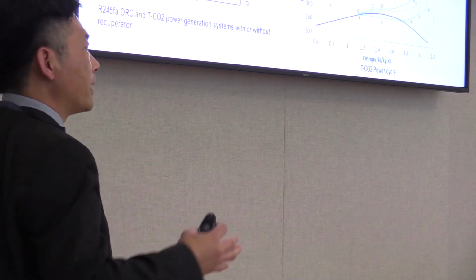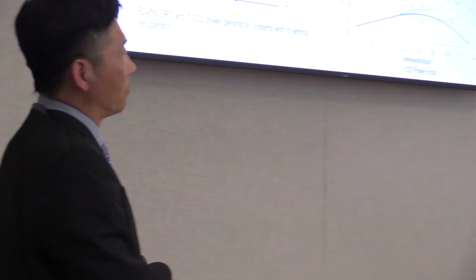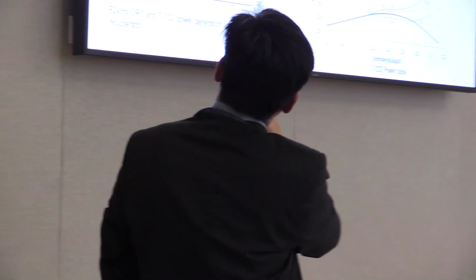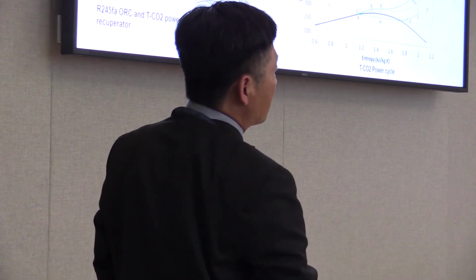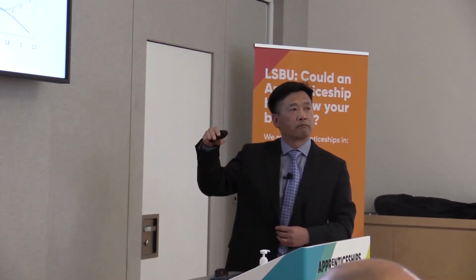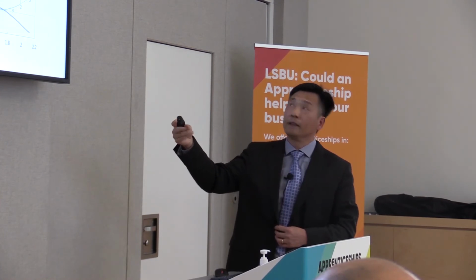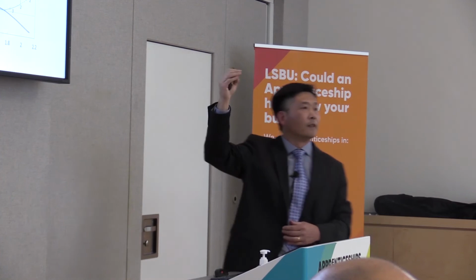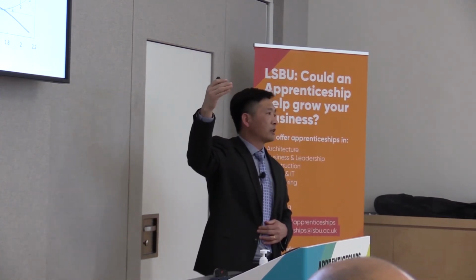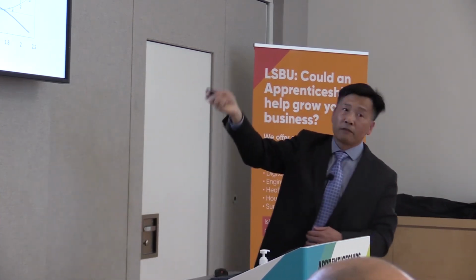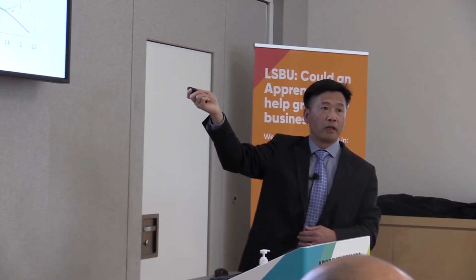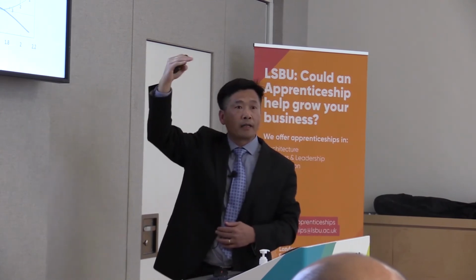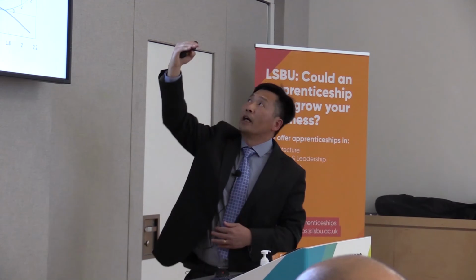So to evaluate these two systems, we need to find out the applicable operating conditions for each working fluid and each power generation system. Because of the critical pressure and the maximum temperature for the ORC system, the maximum heat source temperature needs to be kept within about 400 degrees C. Here you assume the heat source temperature is the same as the turbine inlet temperature. This is just an assumption; actually, there is some temperature difference. And the pressure for the ORC system can be controlled to different values, but you need to make sure that the highest ORC pressure is a little bit lower than the critical pressure.